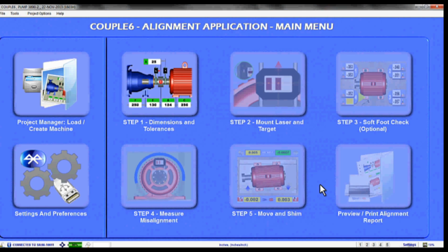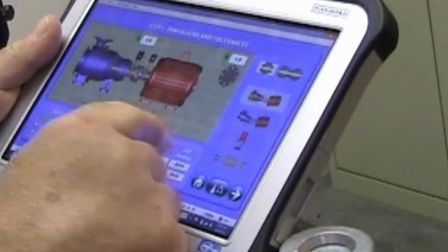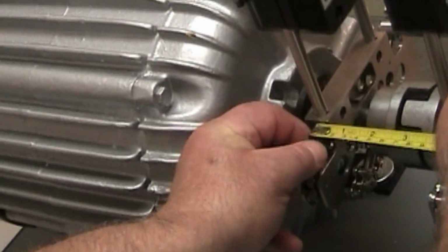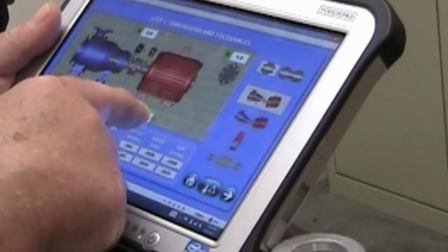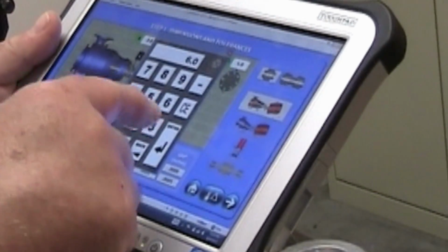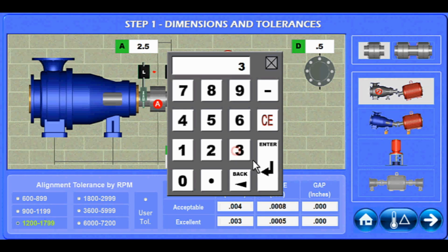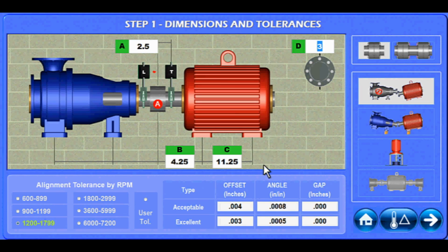Now from the Couple 6 main menu, click on the Step 1 icon to pull up the dimensions screen. Select the coupling and machine types and begin measuring. To enter each dimension, press and hold the entry box to bring up the keypad. Type in the dimension and hit Enter. Continue to measure and enter all four dimensions to an accuracy of 1/4 inch, or 6 millimeters.